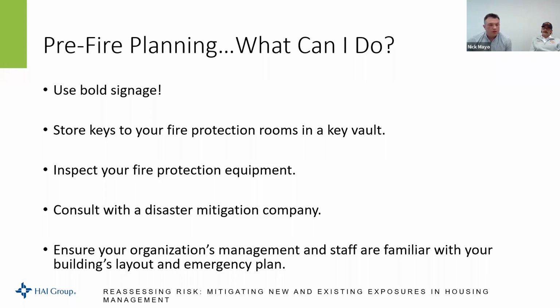Okay, so what can you do during your pre-fire planning? As Paul mentioned before, use bold signage. Your fire protection equipment rooms, your elevator rooms, main electrical rooms, your fire department connection on the outside of the building. One thing with that fire department connection, there should be bold signage that indicates whether that fire department connection is feeding a sprinkler system, a standpipe system, or both. Especially for responding agencies, that's extremely important, because we need to know what the water we're sending from our fire engine going into the building is feeding. So if we think it's feeding a standpipe, and in reality it's feeding a sprinkler, we're trying to put the fire out with the standpipe system, we're not feeding it with any water. So having that signage is extremely important.